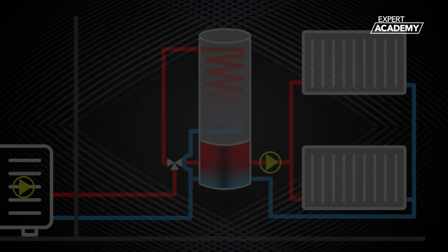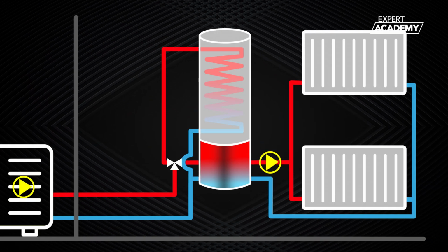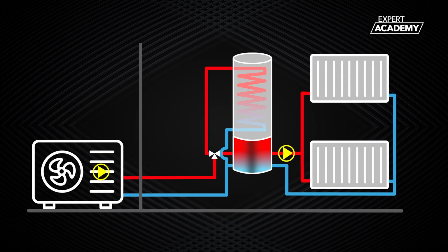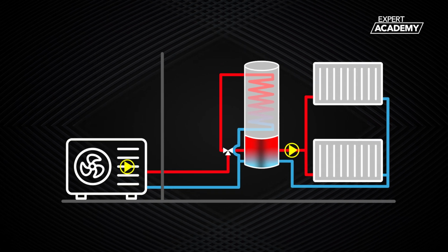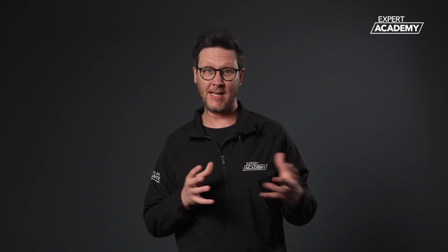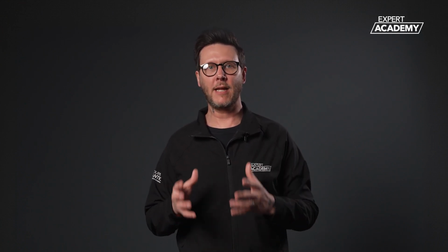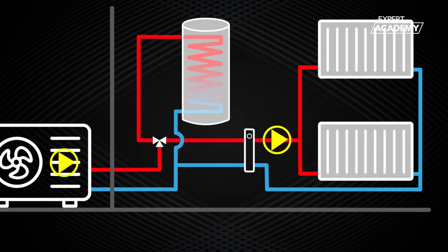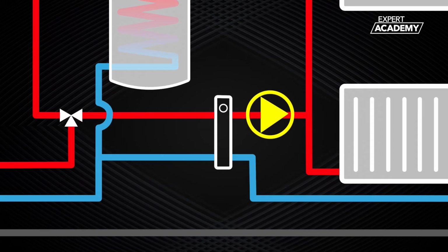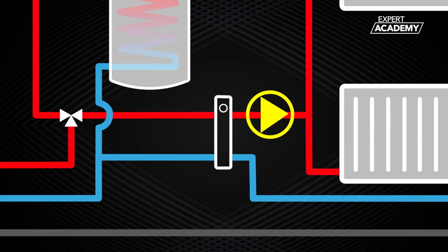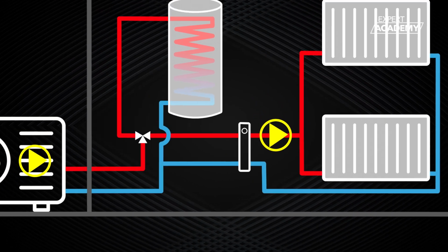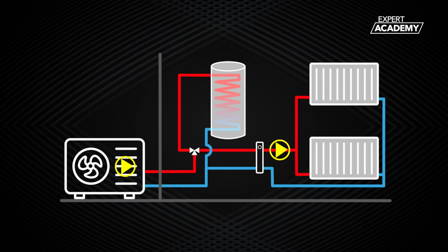Buffers can be standalone or integrated into your hot water cylinder. Integrated buffers can be particularly beneficial in situations where space is limited. This brings us to the third option. If your system requires hydraulic separation, but already has the necessary system volume, you can opt for what is known as a low-loss header. A low-loss header is essentially the same as a buffer, but with a smaller capacity of water, and again, pre-plumbed cylinders with integrated low-loss headers are available.